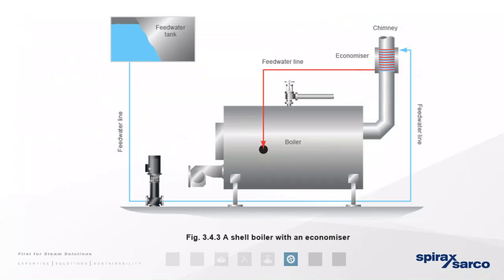So again, a typical layout, very similar to what Alvin was showing. You have your feed tank here, your feed water line into your boiler, coming off an economizer. So it's preheating the water through the economizer back into the boiler. Spirax-Sarco don't actually sell economizers, but we do know the process.